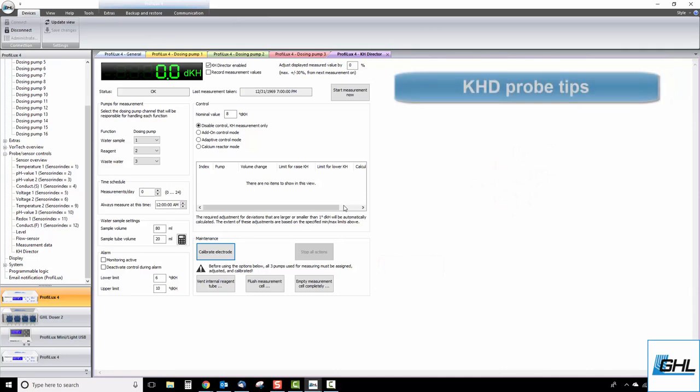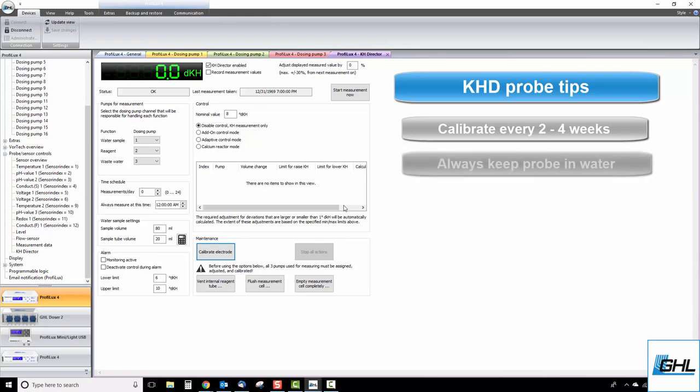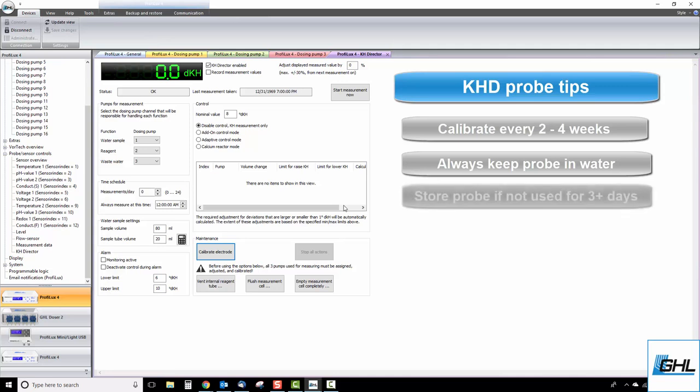When it comes to servicing the probe, we recommend you calibrate every 2 to 4 weeks. Calibrating at these intervals will allow the KHD to maintain maximum accuracy. It's also important to note that the KHD probe should always be kept in water to prevent it from drying out. If your KHDirector does not perform tests for more than 3 days, we recommend removing the probe and storing it in liquid until you're ready to use it again.